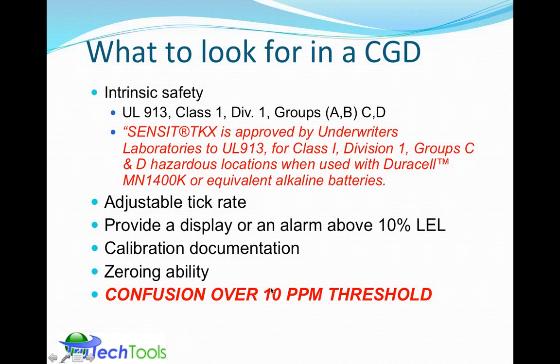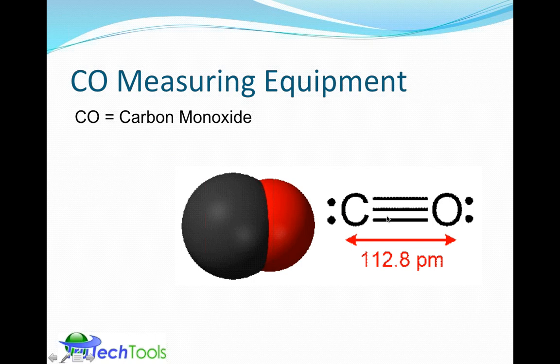You'll notice throughout the standard there is no lower level detectability except this ability to detect the alarm level at above 10%. So there's no threshold, there's no 10 ppm threshold. That's a misinterpretation of what the standard's trying to convey here. Now let's move to the carbon monoxide measuring equipment.